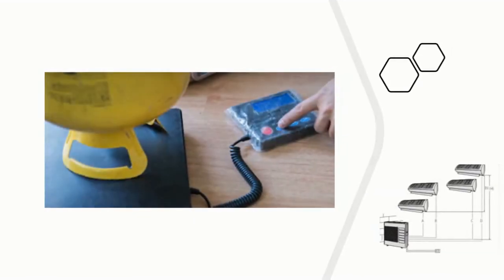Heat pumps are charged with enough refrigerant for a specified length of refrigerant line set. Constant capacity systems are often only provided with enough refrigerant for 15 feet of line set before refrigerant needs to be added. Variable capacity heat pumps usually have enough refrigerant for longer runs. Ensure the contractor charges the system to accommodate the extra length.